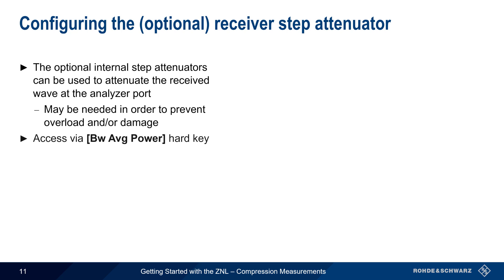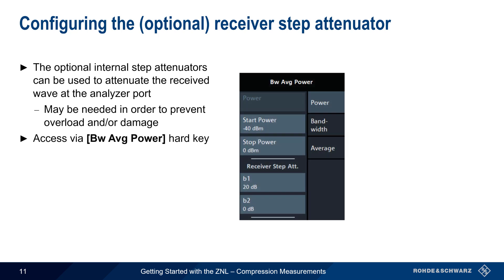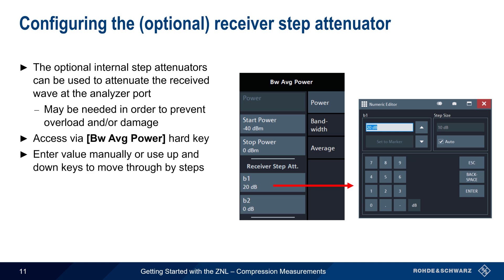Before we conclude this presentation, recall that the optional internal step attenuators on the ZNL can be used to attenuate the received signal or wave at the analyzer port. This sometimes may be needed to protect the instrument from overload or damage, especially when measuring high gain amplifiers. To configure the step attenuators for a given port, press the Bandwidth Average Power hard key, and then select the port to configure. The attenuation values can be manually entered, or the up and down arrows can be used to move stepwise through this range. On the ZNL, attenuation can be configured from 0 to 30 dB in steps of 10 dB.